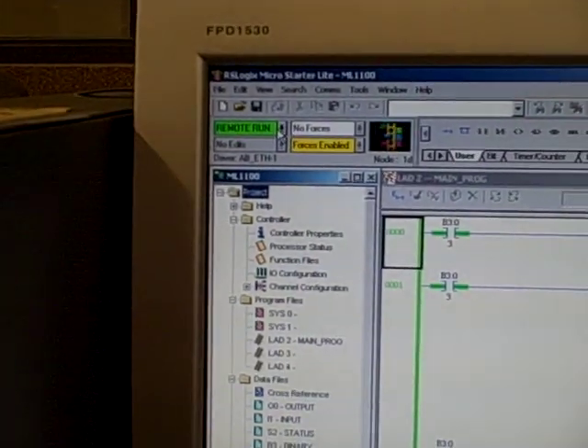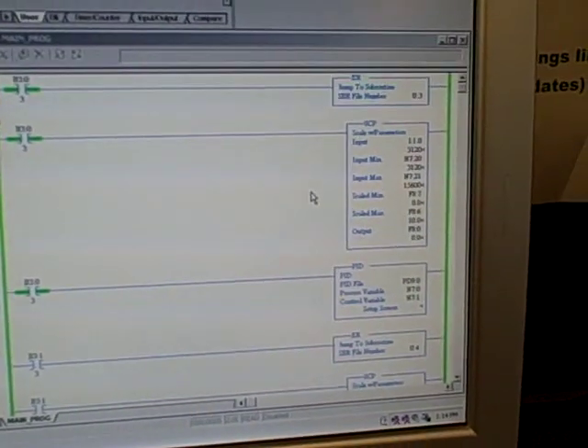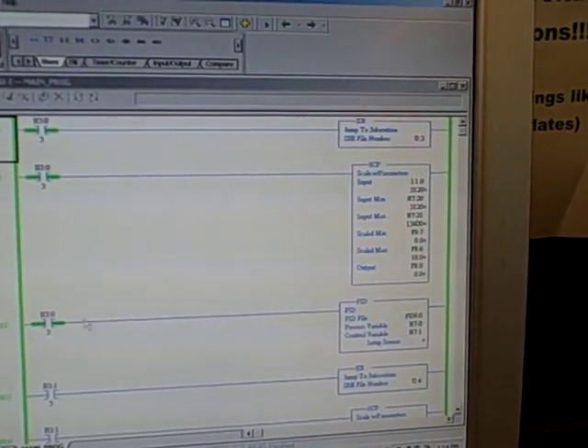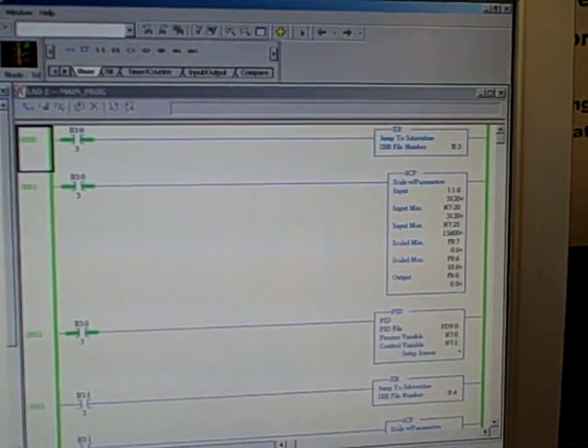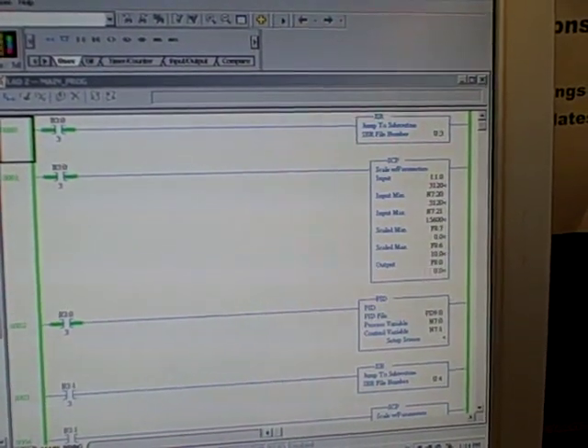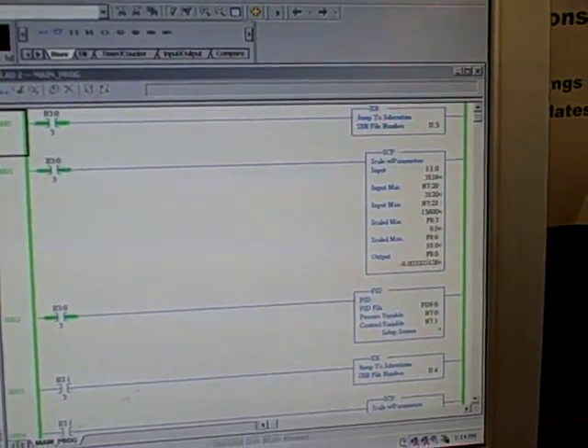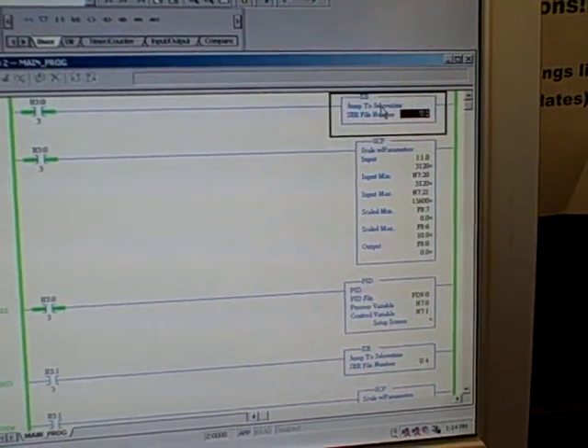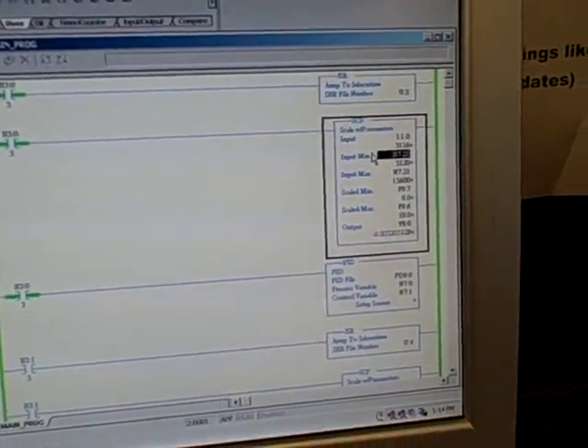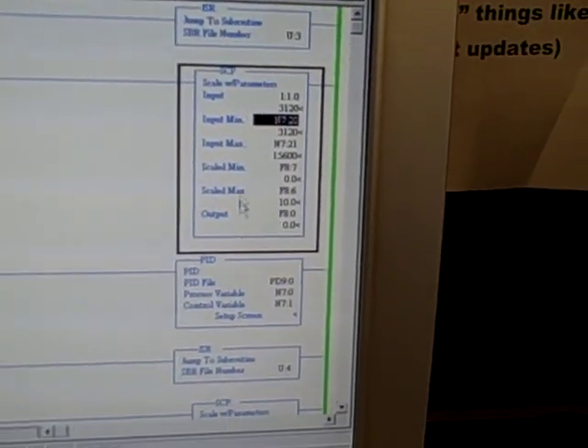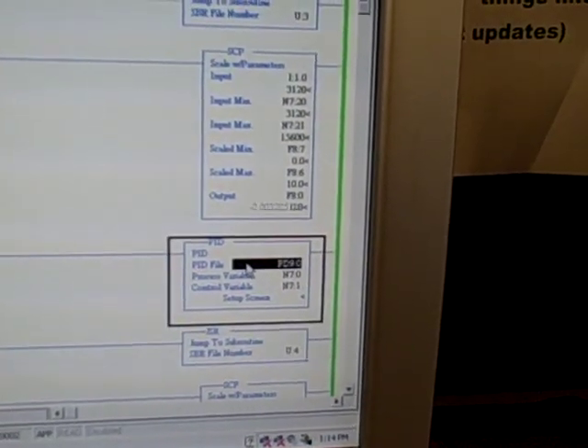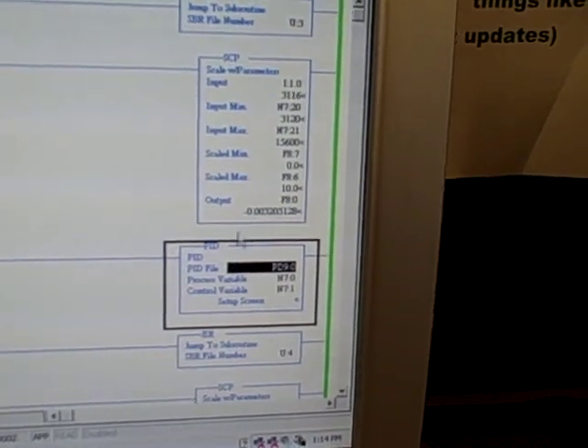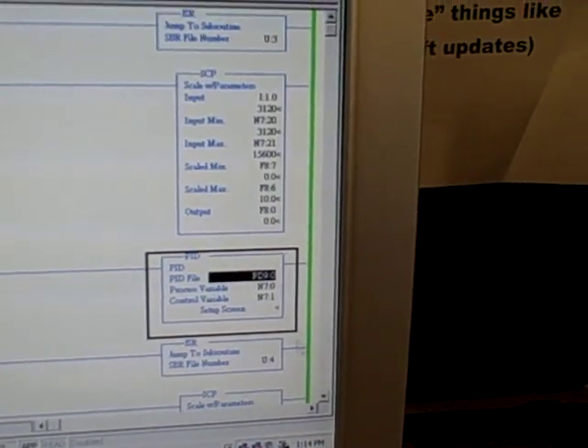I'm in remote run mode right here, and you can see a few instructions. Most of the program is hidden in subroutines. All we see here is the main program page, and on this main page we have a subroutine jump instruction, a scale parameters instruction, we have a PID instruction, and that's for the first PID loop, loop 0.